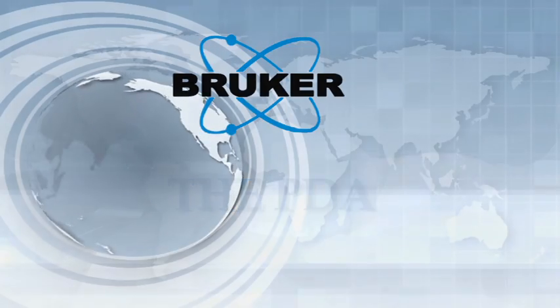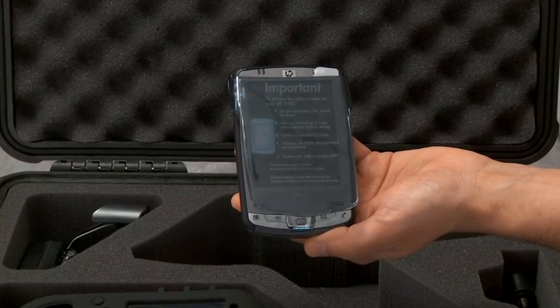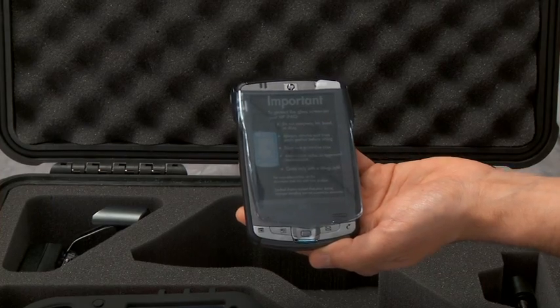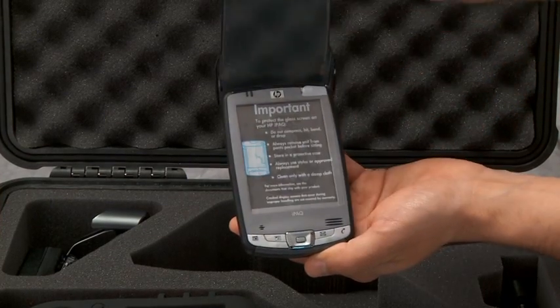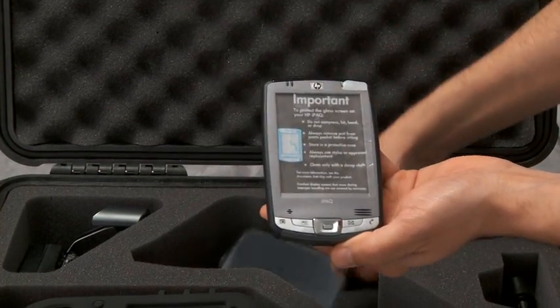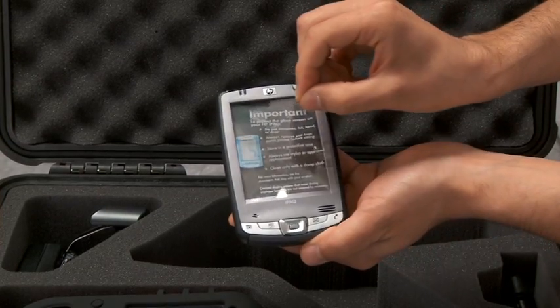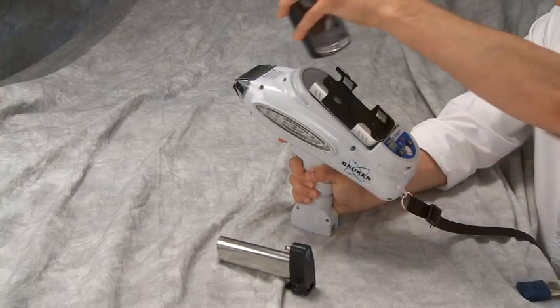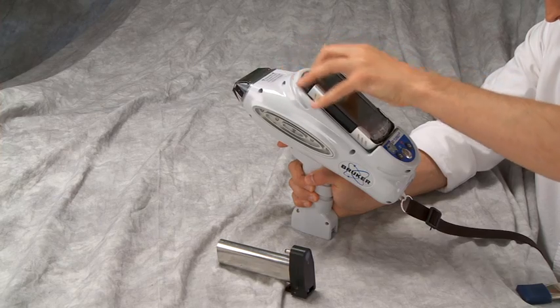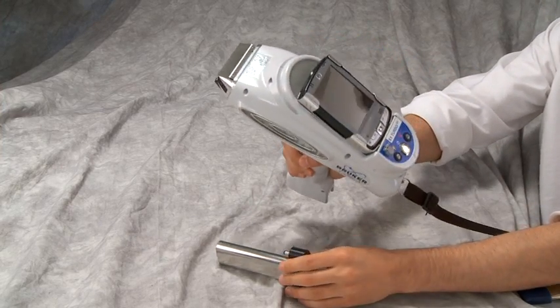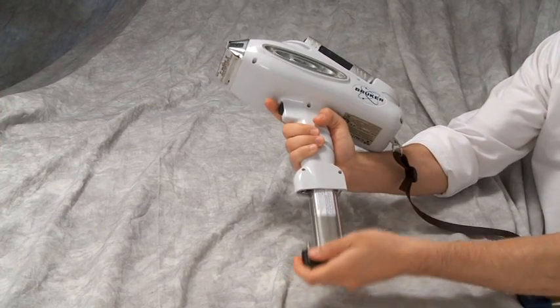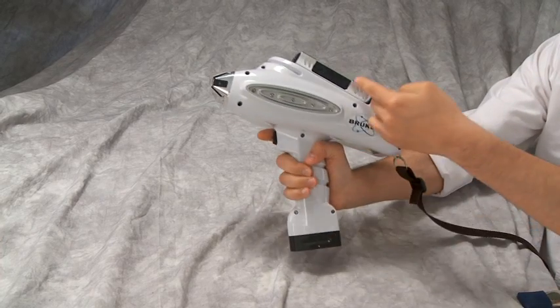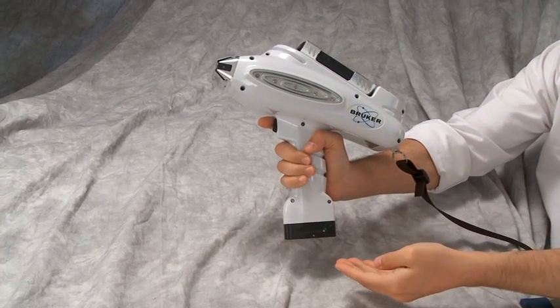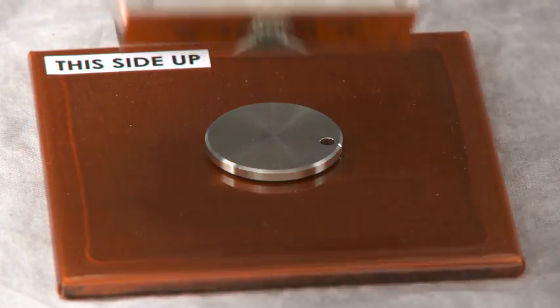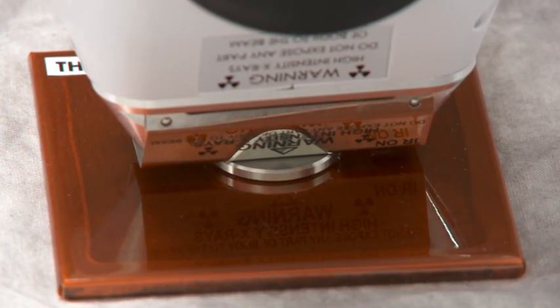The PDA is the main computer controlling and operating the analyzer. In order to prepare the PDA for use, simply remove the plastic and protective covers. Store these parts in the case for future shipping protection. The analyzer and the PDA are battery-powered. When operating the analyzer, the PDA draws power from the handle battery of the analyzer. To get the maximum operating time for the analyzer battery, keep both the analyzer and the PDA completely charged.